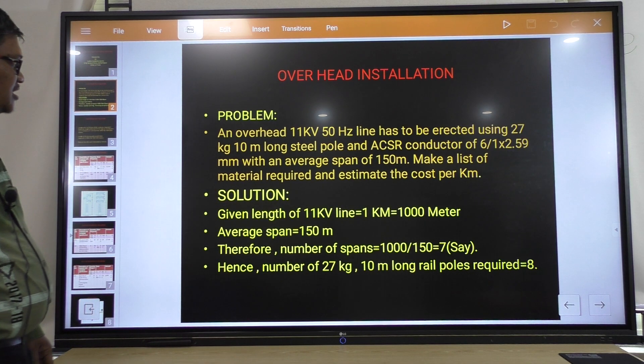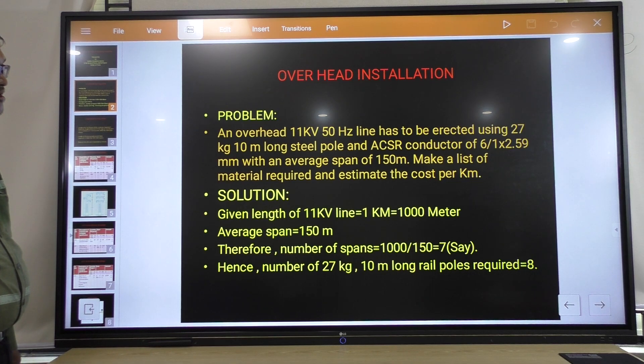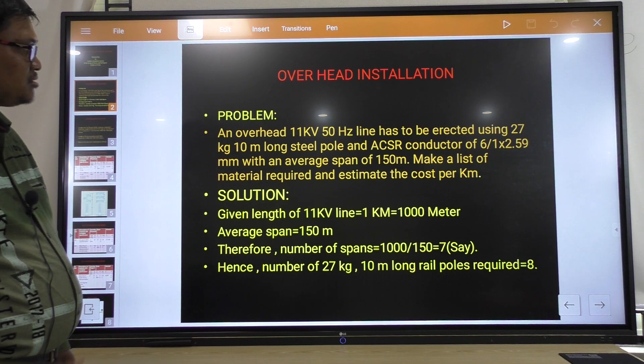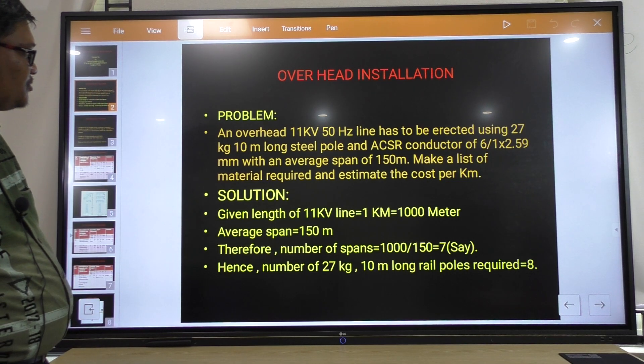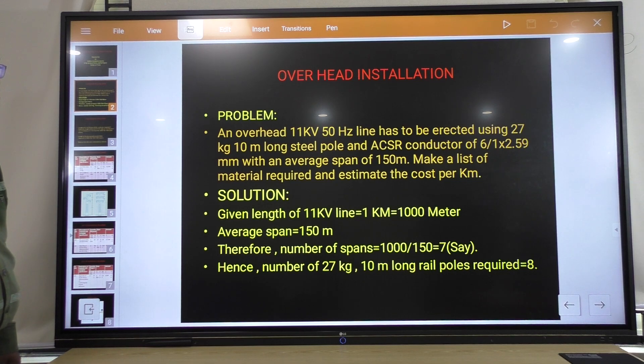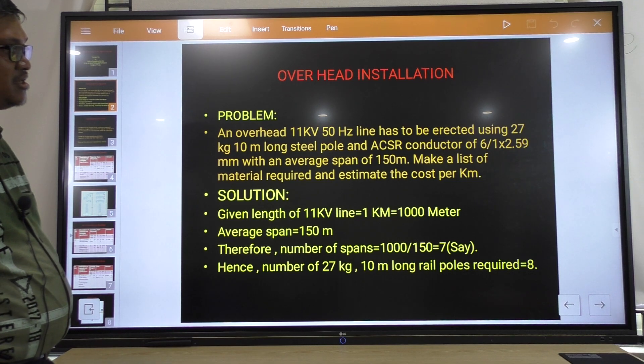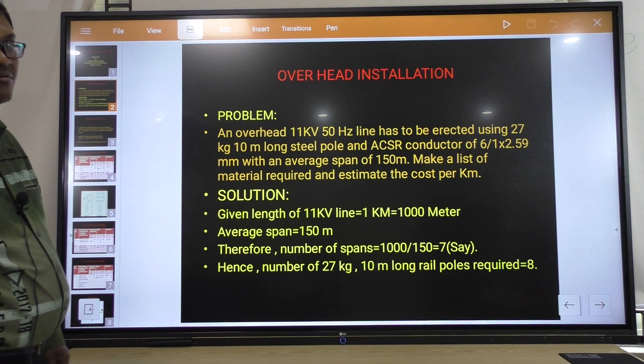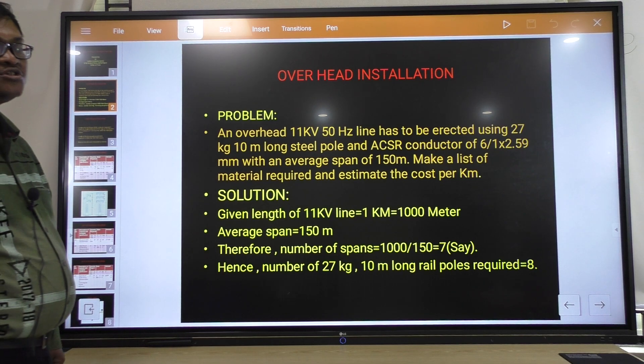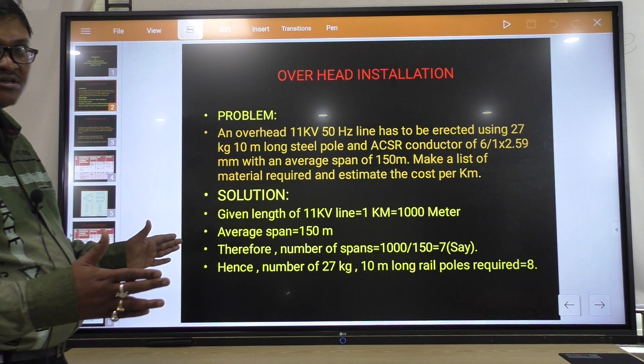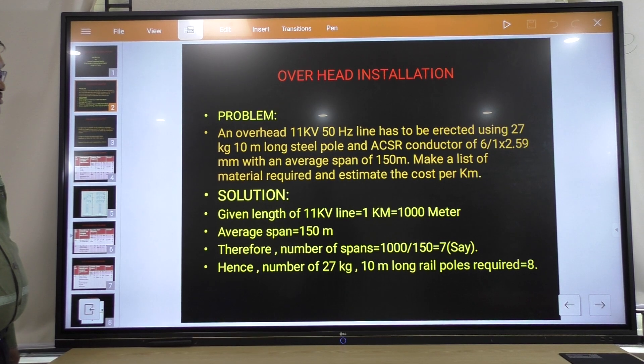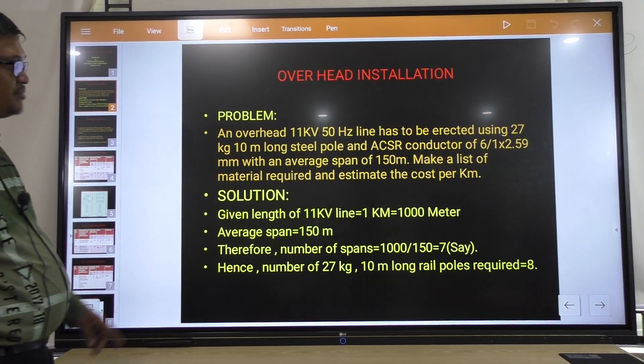Suppose the problem is like this: an overhead 11 kV, 50 hertz line has to be erected using 27 kg, 10 meter long steel poles. The ACSR conductor specification is 6 by 1 into 2.59 mm with an average span of 150 meter. Span is the distance between 2 consecutive poles, so here the average span is 150 meter.